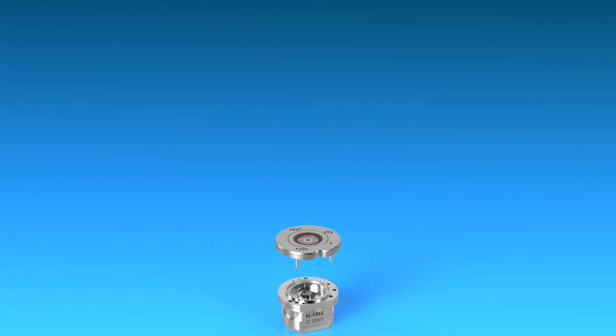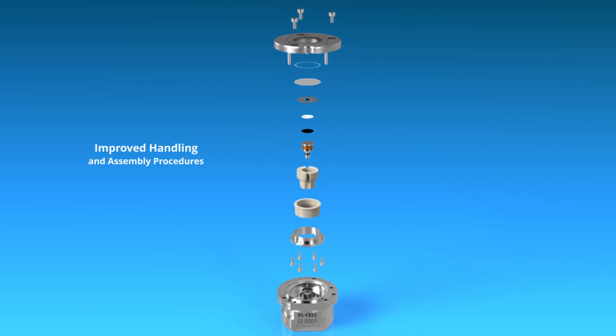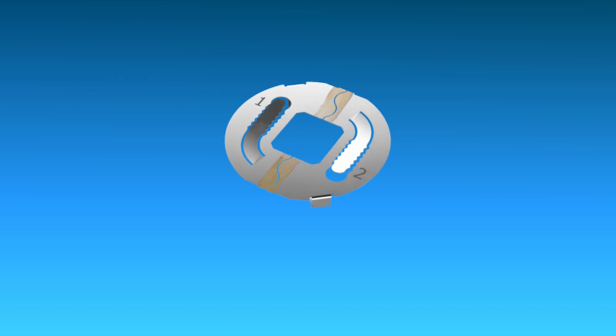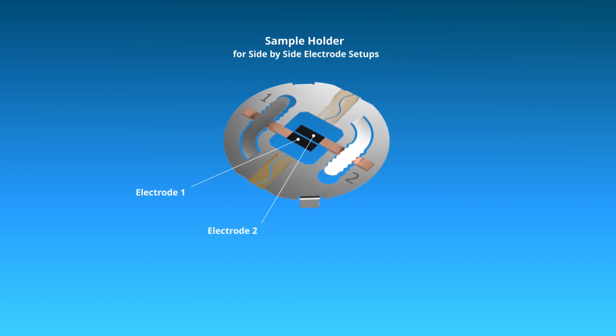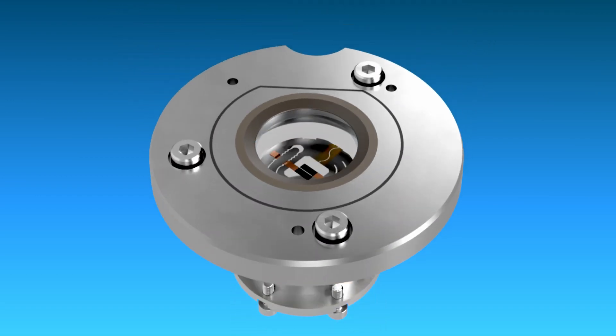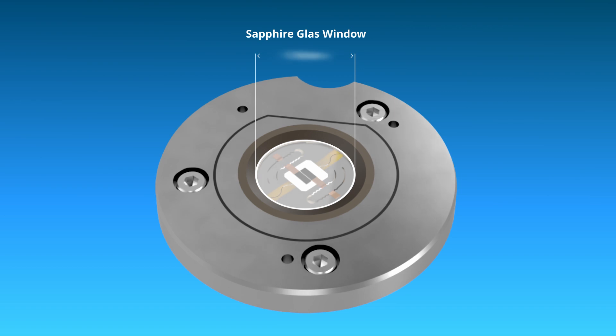The cell itself is much easier to assemble compared to previous designs. The new dedicated sample holder for side-by-side arrangement of the electrodes shortens the preparation time significantly. The much larger lid opening of 18 mm further improves the handling of the cell. Other lids as well as sample holders are available as accessories.